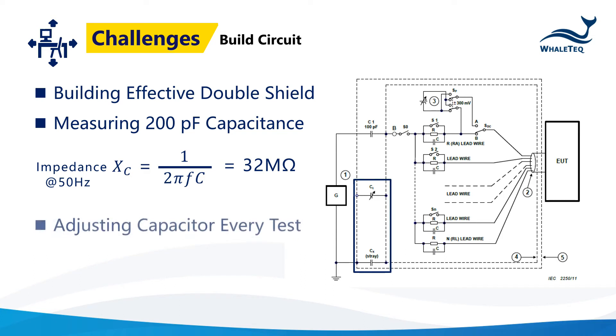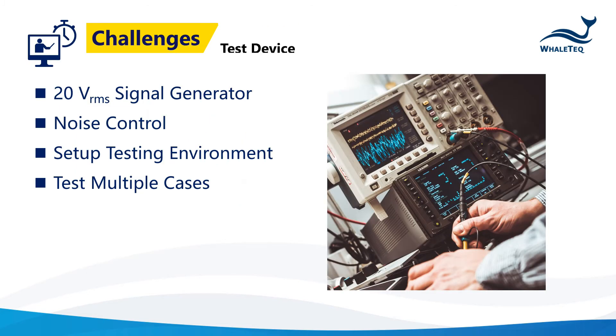Challenge 3: The stray capacitor will need to be adjusted every test due to the sensitivity to the testing environment. Finally, once you get your circuit calibrated, you're ready to test. Per the standard, you need to find a signal generator that can provide a voltage of up to 20 volts RMS without causing significant noise.